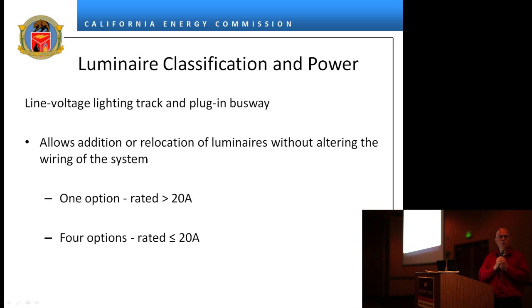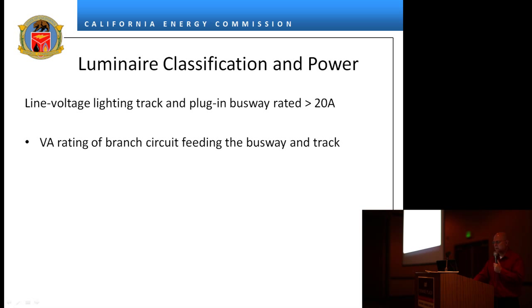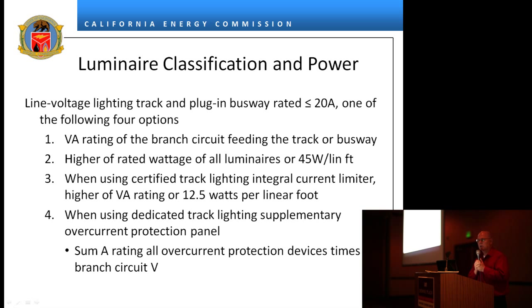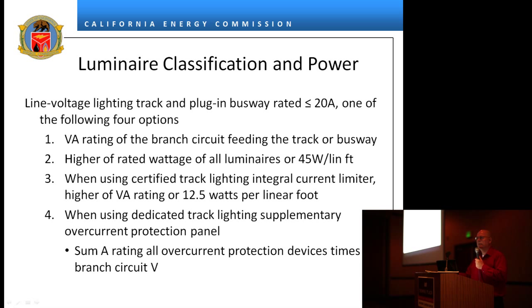For line voltage track, there are basically four different options. If you have a higher VA rating and you're greater than 20 amps, it's only the VA rating of the branch circuit. If you're 20 amps or less, the four options are: the VA rating of the branch circuit, the higher wattage of all luminaires, 45 watts per linear foot, or — if you use a track lighting integral current limiter certified to the energy commission — the VA rating of the current limiter or 12.5 watts per linear foot. You cannot put a 1-amp breaker on 100 feet of track and expect anyone to believe that's honest.